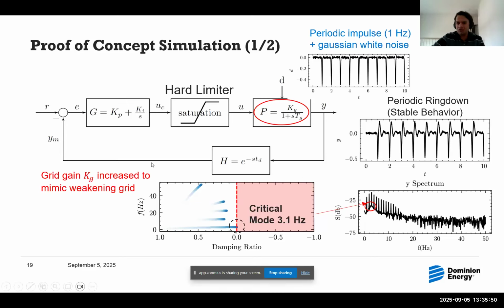So we have a feedback control here, with a time delay in feedback as you'd expect. In this case, we'll study what happens if we change the gain of the grid, which is essentially what happened when we removed nearby generators, and see how this creates an oscillation with the help of limiters and an unstable feedback control.